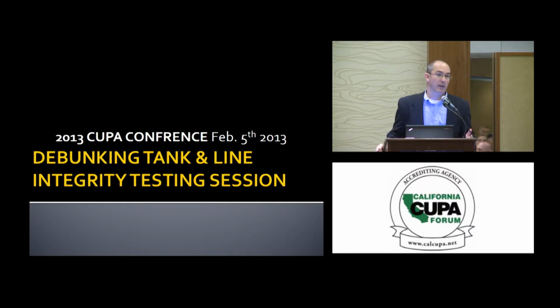Now, that would not apply if it's been determined that there is no water table around the tank. If that's measured through a well point or something, so it's known that the water table is below the tank, or for instance with a double wall dry interstitial tank that would have no chance of water ingress. And because it's not volumetric, there's no waiting time between delivery and testing of the tank.